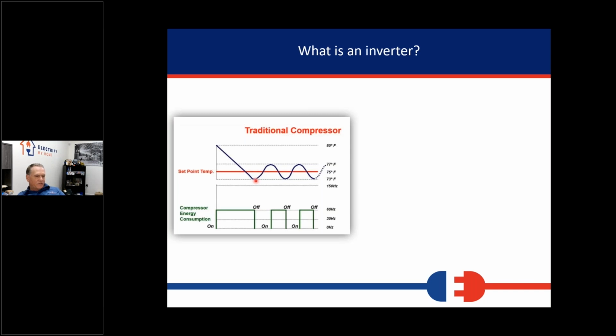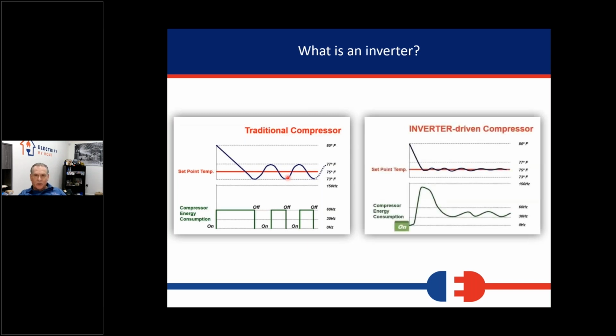Then it shuts off, and it lets all the energy come back into the house and takes it all out again. So basically this is doing a seesaw effect - it gets the air nice and cool, shuts off, the heat from the house gets into the air, the unit comes back on, and it does this - they never really run long enough to actually condition or provide real comfort. That's why for ultimate energy efficiency, comfort, and customer satisfaction, we love the inverter-driven compressors.